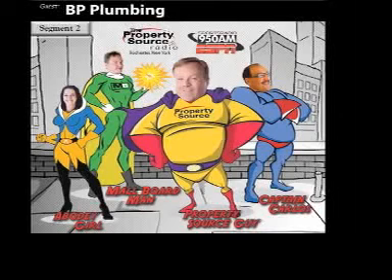There's two common models used here in the area, the R75 or the RC98. The R75 is about 82% efficient. The RC98 is over 96% efficient. It captures more of the energy through a separate condensing coil. Also, with the condensing unit, the RC98, you get more gallons per minute, about 2.5 gallons more per minute.